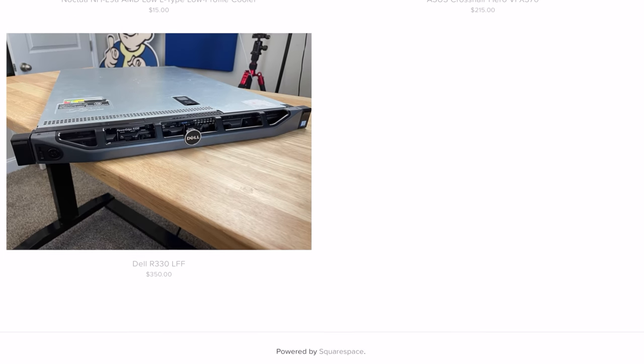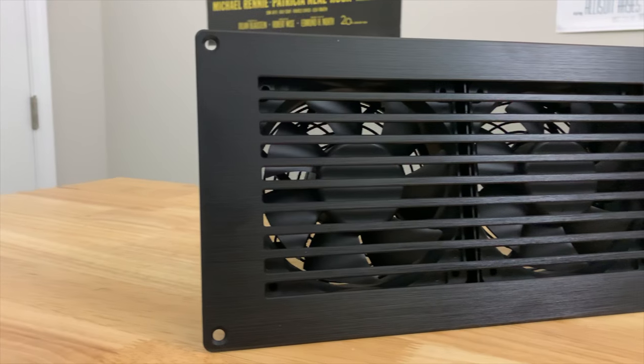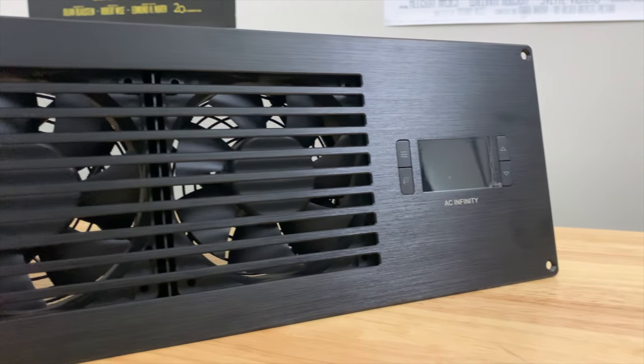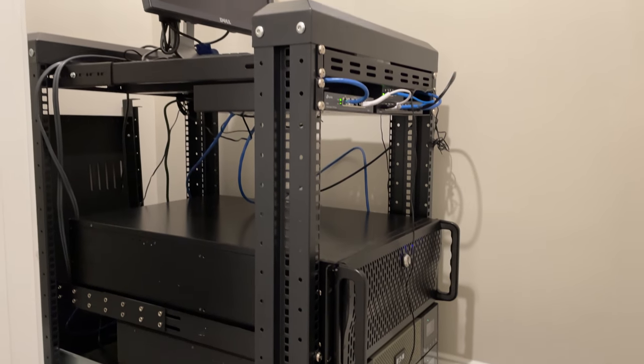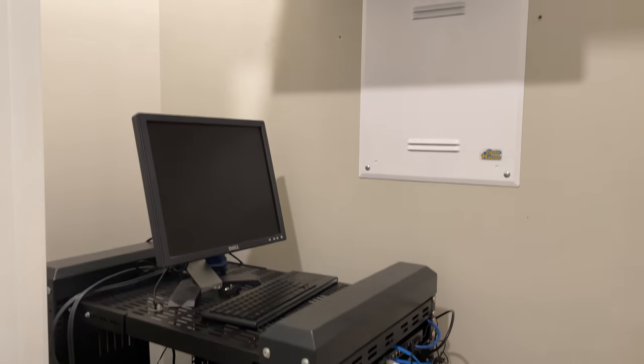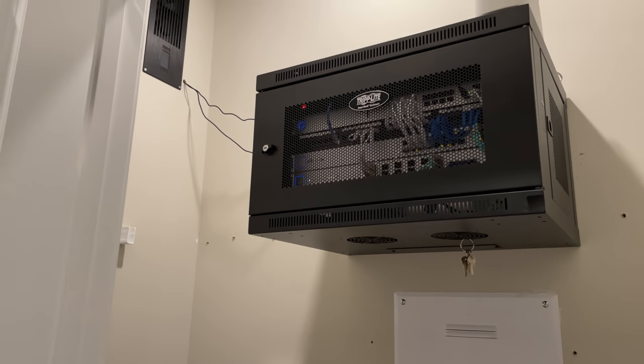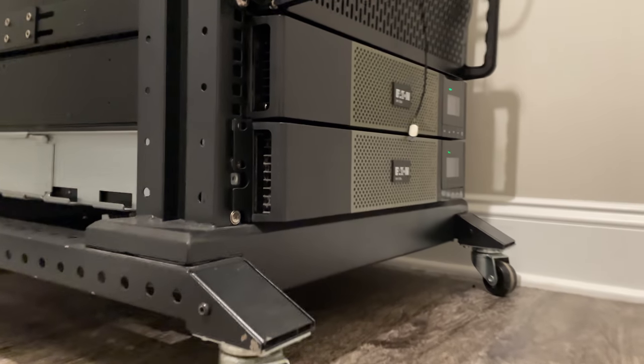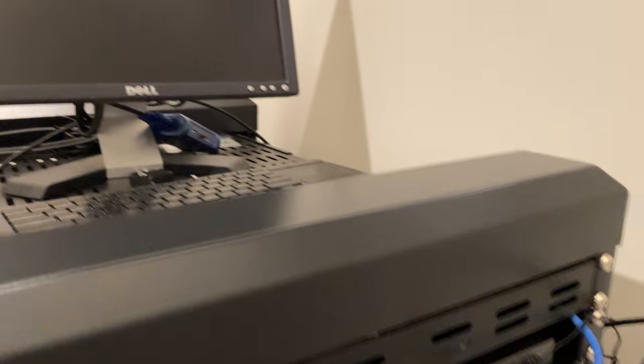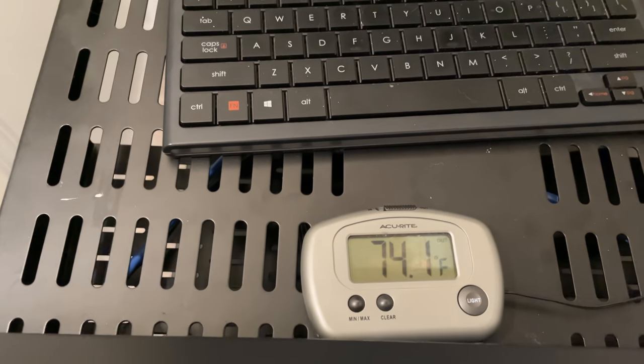The Airframe T7 has actually been doing a pretty decent job in my opinion, and the temperature of the room has basically fluctuated between 80 degrees Fahrenheit and 88 degrees Fahrenheit throughout the year. While that does sound hot, you have to remember that temperature is being recorded above all the actual equipment from two different thermometers, and while they do slightly disagree, they're fairly consistent. The air coming into the room is somewhere between 71°F and 76°F depending on the ambient temperature of the house or the air outside.